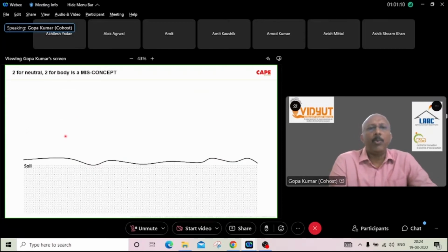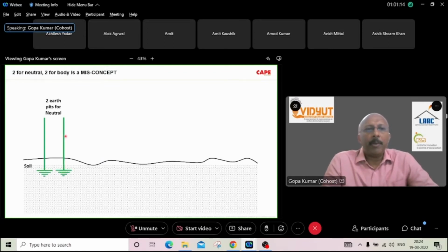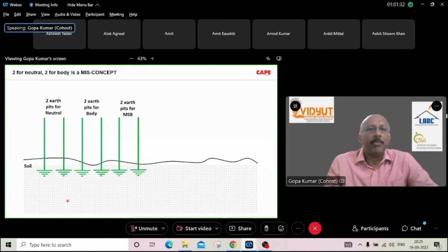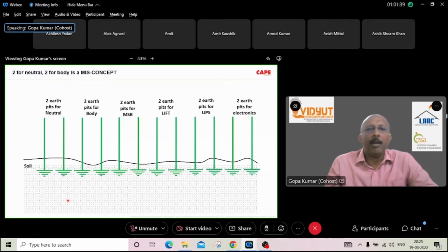And what do we do in the name of earthing? Transformer neutral, two separate copper pipes or copper plates to earth pit. Each transformer, each DG has got two strips running and connected to a plate in soil. Body, again two more. Main distribution board, again two more. Lift, again two more. UPS, again two more. Electronic equipment, again two more. Something is called clean earth, isolated earth, and all these.